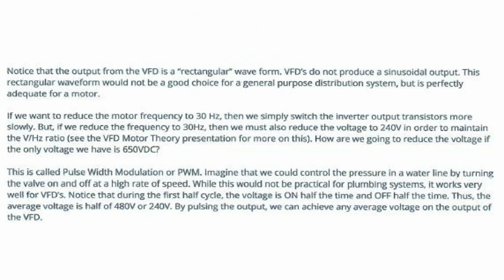So the signal from the drive to the motor is basically a square wave. And when we switch the frequency, we likewise have to change the voltage to match the drop in frequency. It's a pulse width modulated signal. That's pretty much how a drive operates. It's simply a pulse: more ons, less offs, the faster the motor spins. More offs, less ons, the slower the motor spins.